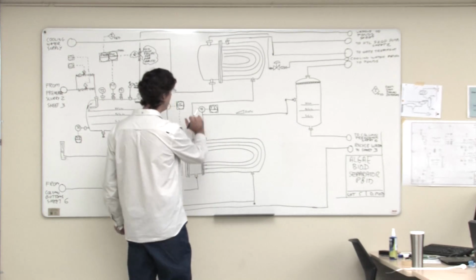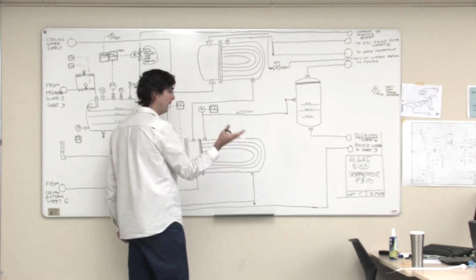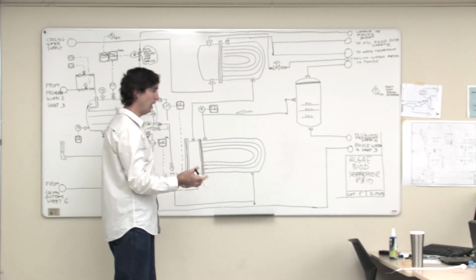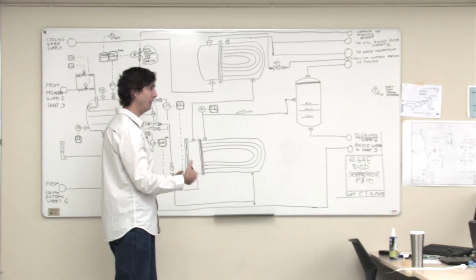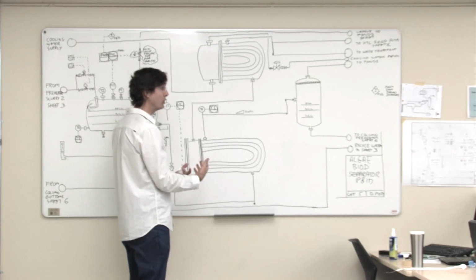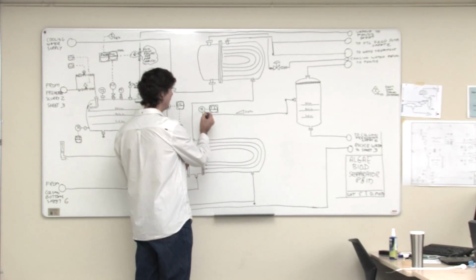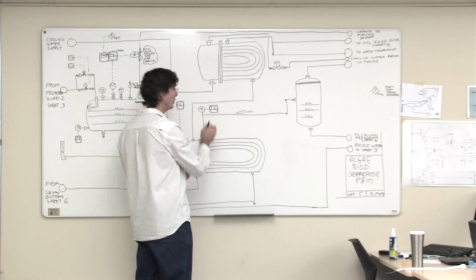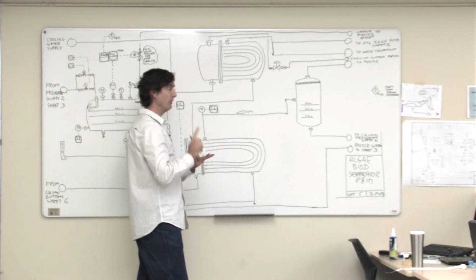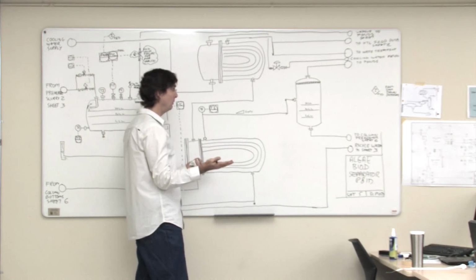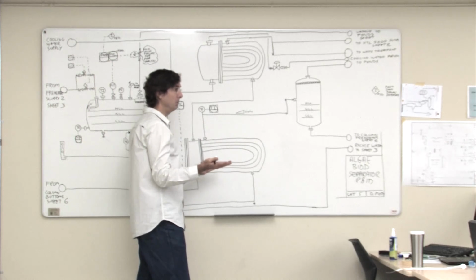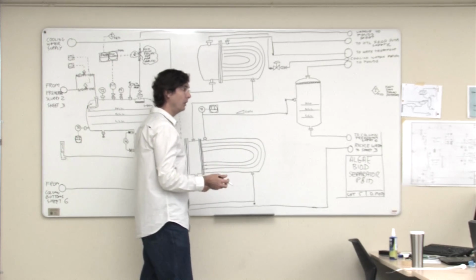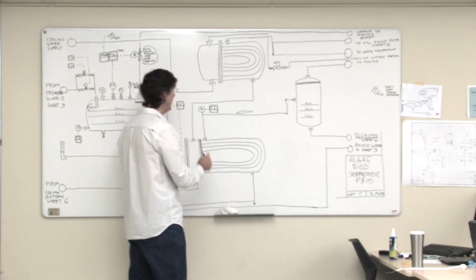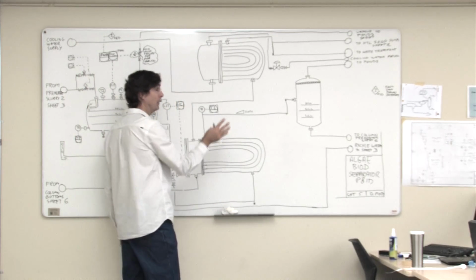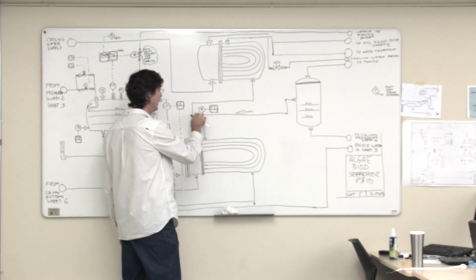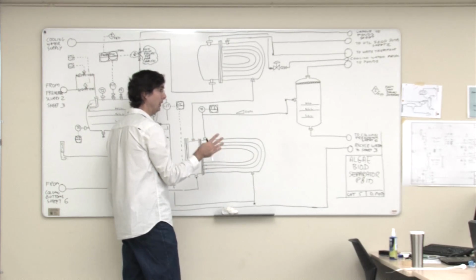You might put the TE in and just leave it as bare wire, and then somebody would have to walk around with a handheld device, plug it in, and measure the temperature. If you're trying to save money, because the wire from that TE back into the DCS requires paying for wiring, conduit, and software configuration, you might save a couple thousand dollars, not that much. So for you guys, every TE would come with a TI. I've very rarely seen us put a TE in and not wire it back into a DCS.